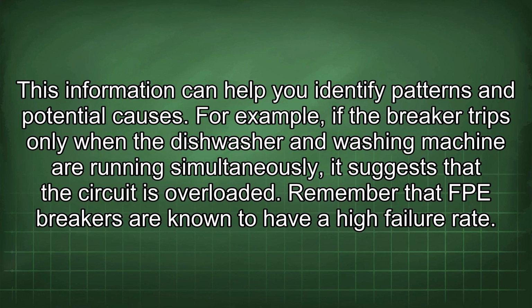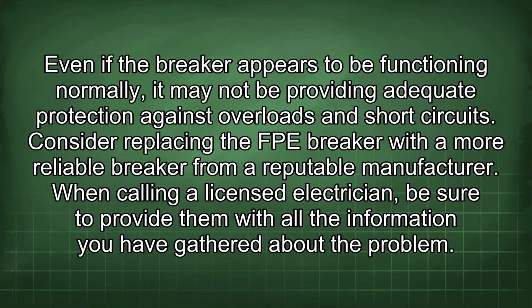overloaded. Remember that FPE breakers are known to have a high failure rate. Even if the breaker appears to be functioning normally, it may not be providing adequate protection against overloads and short circuits. Consider replacing the FPE breaker with a more reliable breaker from a reputable manufacturer.